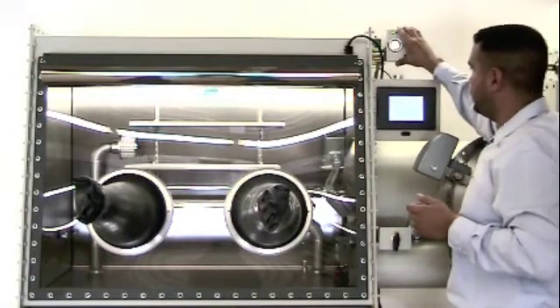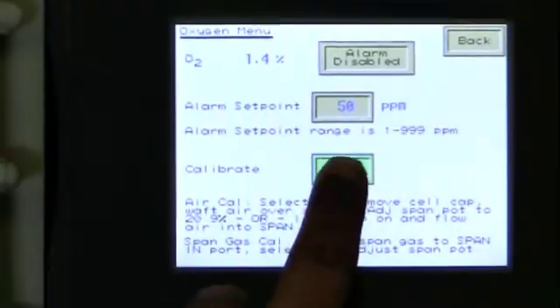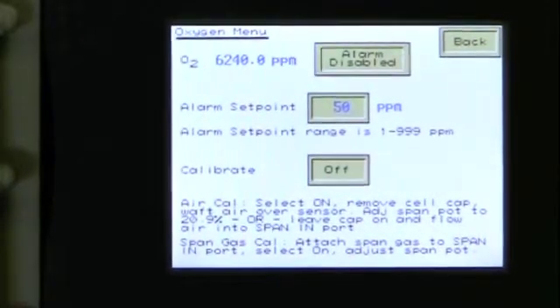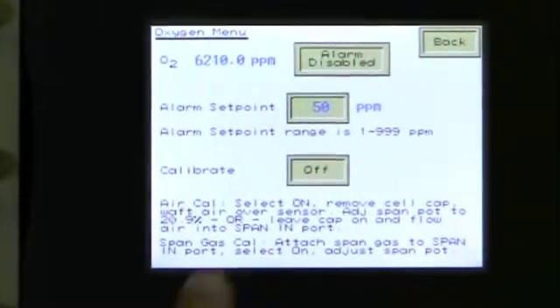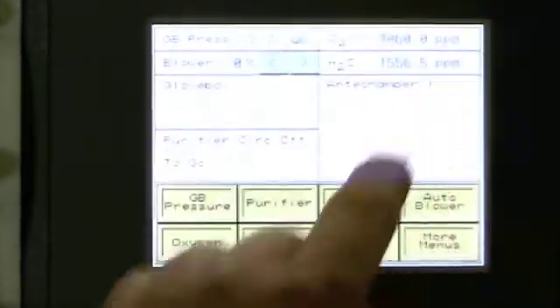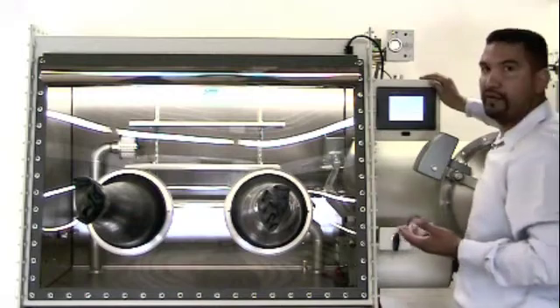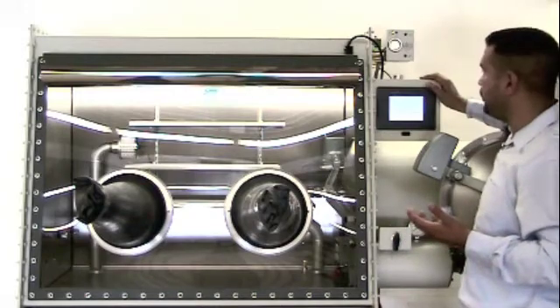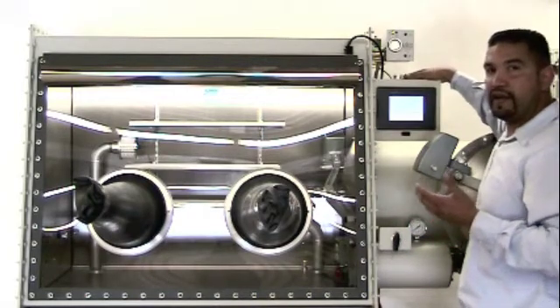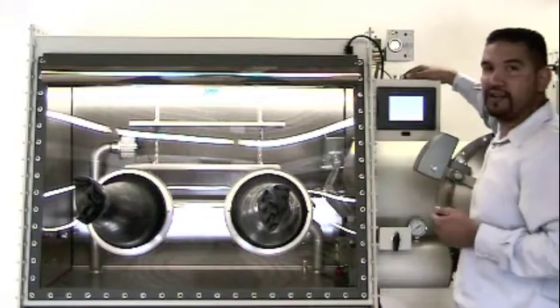Once you have made your adjustment, simply deactivate the calibration routine and press back to return to the main menu. You should now observe that the oxygen readings are trending down. And that is how you calibrate the Nexus 2 oxygen analyzer. Thank you.